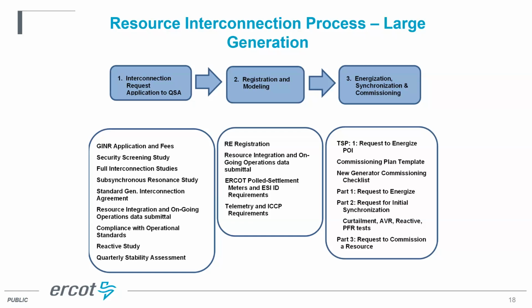Sometimes they have to do a subsynchronous resonance study. They determine the need for it during the screening study, where the Dynamic Studies Department checks if it's within N-1 contingencies of the series capacitor. If so, it'll have to do the subsynchronous resonance study after the FIS, and that's usually contracted out or done by the TSP as well.